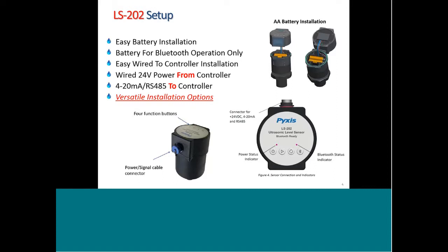And you can, again, wire this into any controller, either using a 4 to 20 milliamp or an RS-485 Modbus connection. The beauty of RS-485 is that for those customers that actually don't have a controller and they want to wire this data directly into their network system or their DCS system, they're enabled to do that with this product line simply by landing that directly to the network.